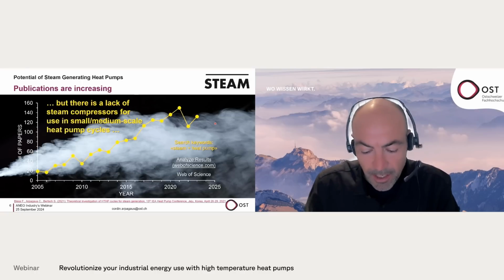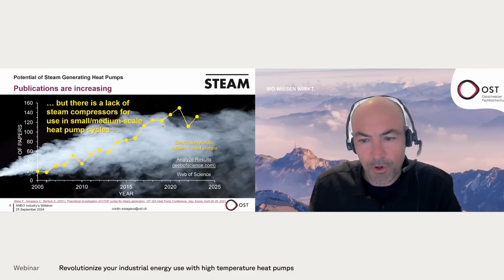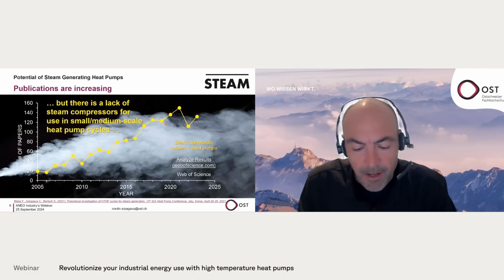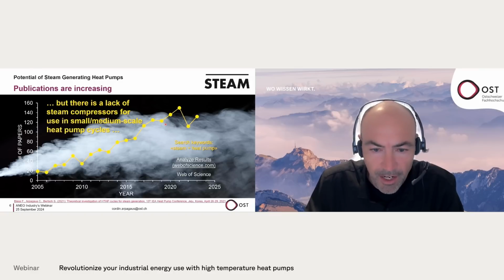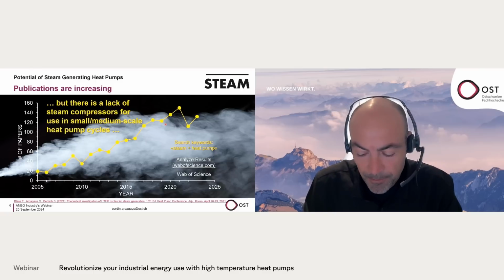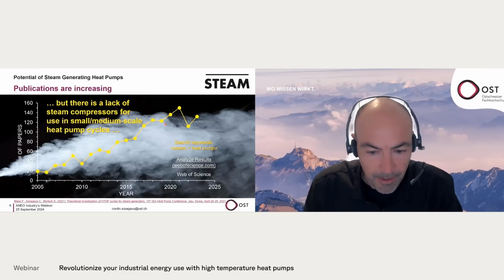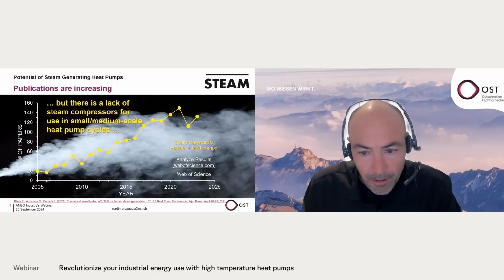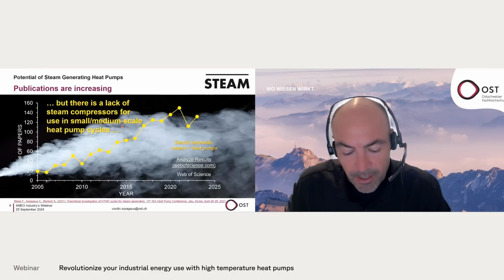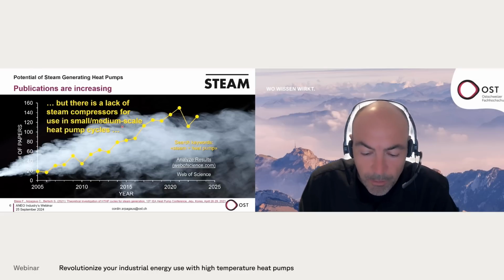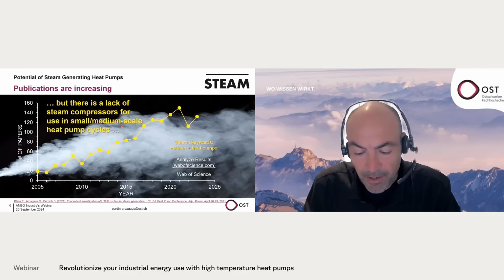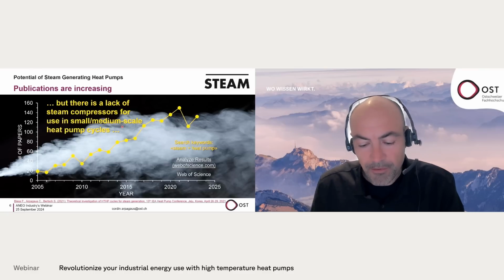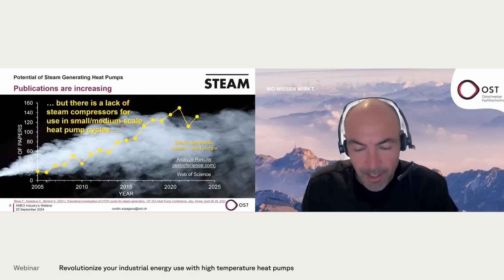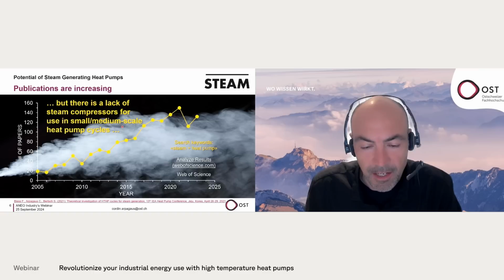When we look at the research status, I'm from a university of applied sciences. We also see a trend towards more and more publications, and this is quite worldwide. Leading are Europe, but also China, for example, is very much developing heat pumps in their provinces. But there is a lack of compressors, and that's a main message. So steam compressors in a rather small to medium size range are quite rare. There are very large steam compressors available from older times from many companies, but reducing the capacity to a 1 megawatt size, let's say, there is still a development need.